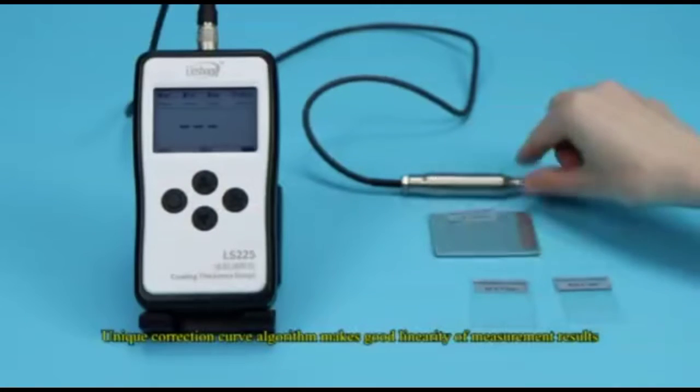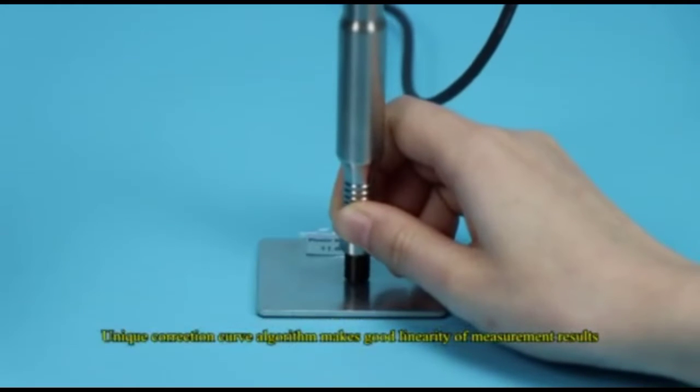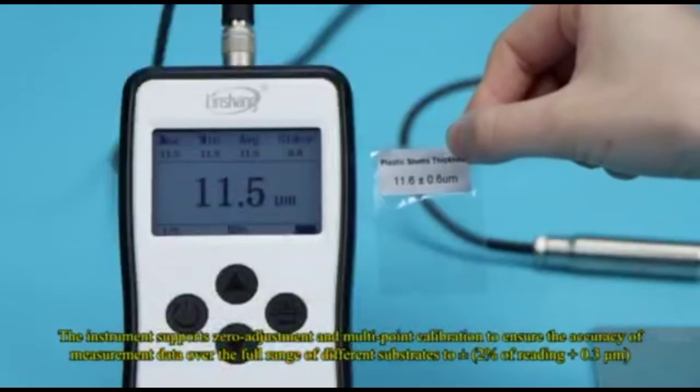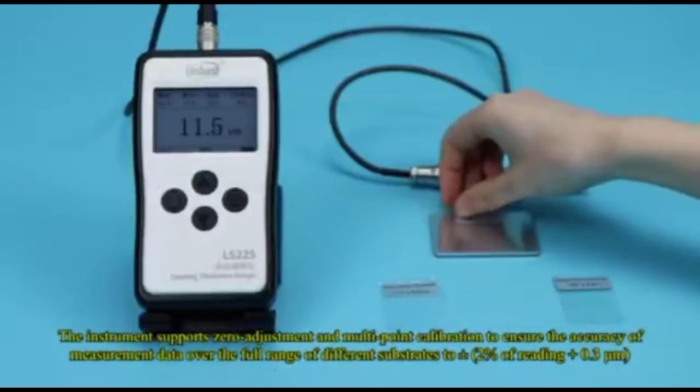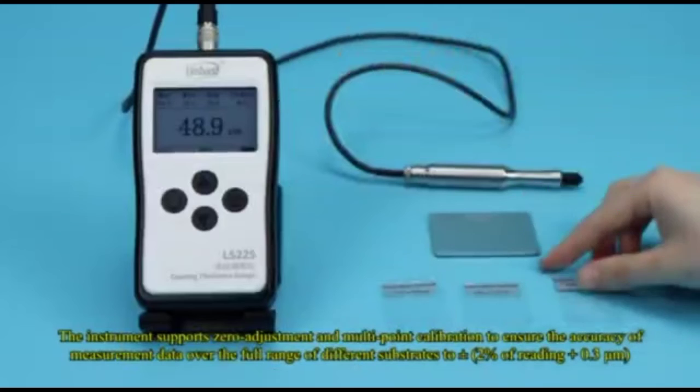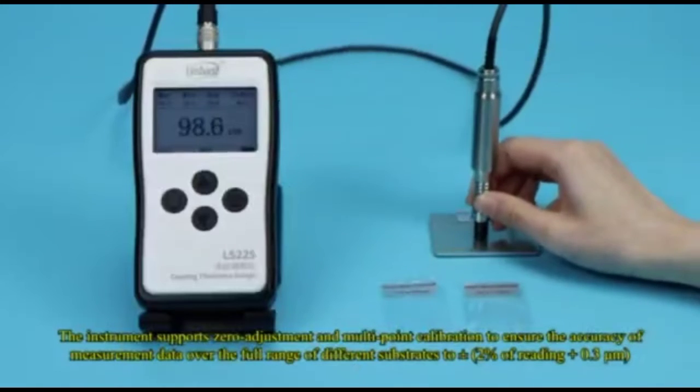Unique correction curve algorithm makes good linearity of measurement results. The instrument supports zero adjustment and multipoint calibration to ensure the accuracy of measurement data over the full range of different substrates to plus or minus 2% of reading plus 0.3 micrometers.